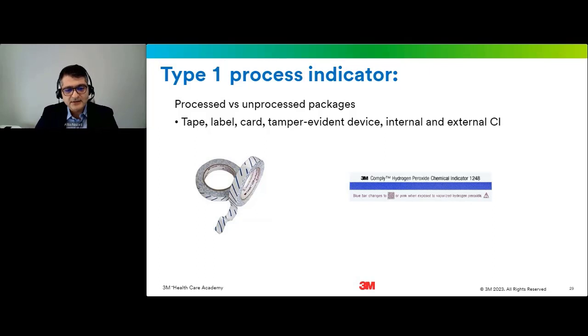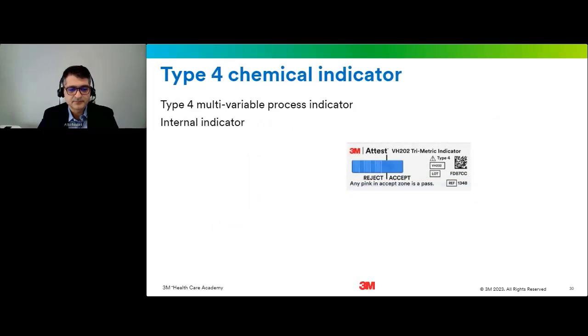So type 1 indicator shows, as I mentioned, processed versus unprocessed. They can be in the form of tape, label, or card. They can be tamper-evident devices. They can be internal or external CI. You can see examples of two types of type 1 indicators in this slide. Type 4 indicators, as we said, are multivariable process indicators and internal indicators. This is an example of that. Type 4 responds to three critical parameters: the exposure time, the temperature, and the concentration of the vaporized hydrogen peroxide.